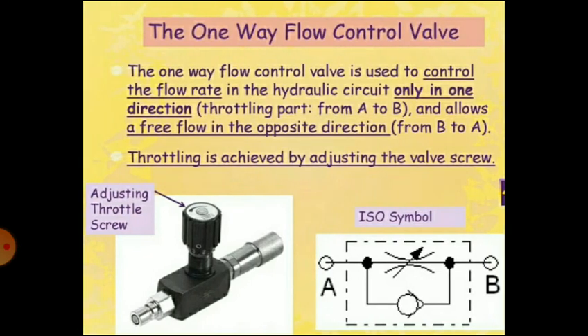The one-way flow control valve is used to control the flow rate in a hydraulic circuit only in one direction — that is, throttling from port A to port B — and allows free flow in the opposite direction, from B to A. Throttling is achieved by adjusting the valve screw.